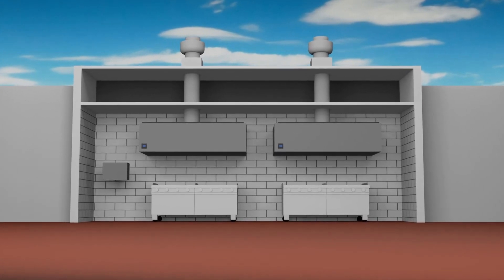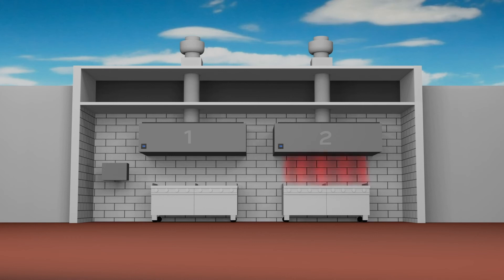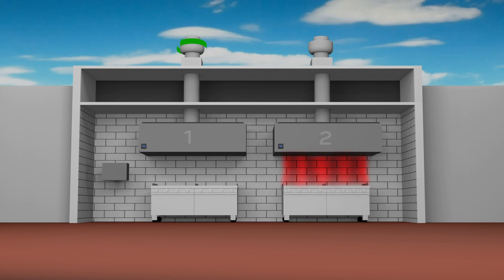If you wire the temp sensor in hood 2 to where the sensor for hood 1 should be, when you start your appliance under hood 2, like a solid fuel charbroiler for example, the sensor will warm up but the fan for hood 1 will speed up. If this happens, you run the risk of setting off the hood fire system because you won't be moving enough air and overheating will occur.